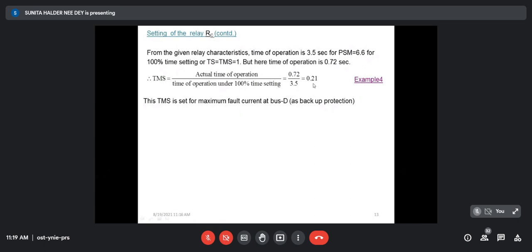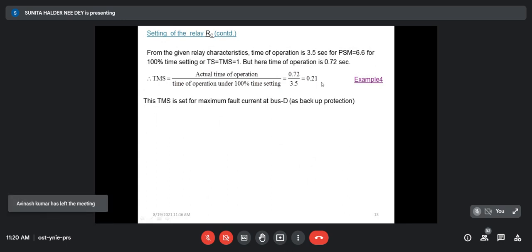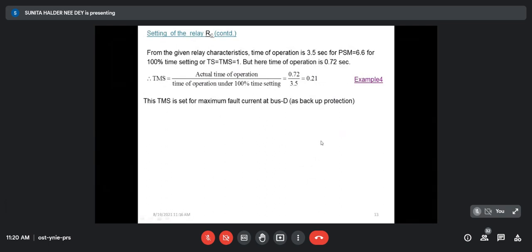For academic purposes, let us keep it at 0.21. This TMS is fixed — when set for relay C as backup protection, the same TMS of 0.21 applies for primary protection too, because you cannot open the relay online and reset it every time, otherwise the protection system will be hampered. In practical case, it should be 0.2.